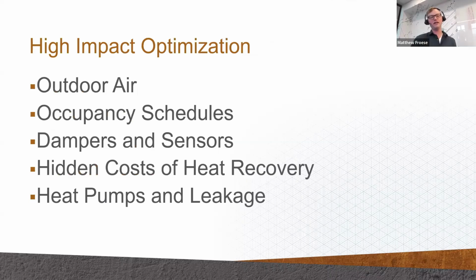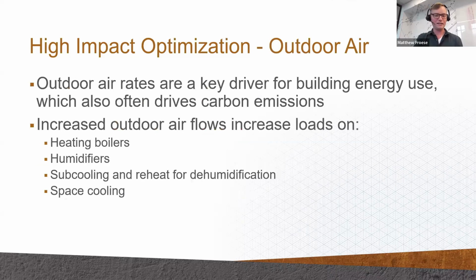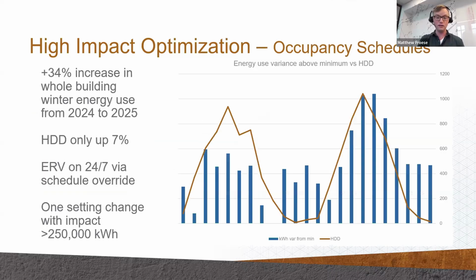So some areas of high impact optimization here. We're going to talk a little bit about outdoor air and ventilation management, a little bit about occupancy schedules, really basic fundamentals, some stuff about dampers and sensors, a little bit about heat recovery, and then heat pumps and refrigerant leakage. I'm going to move fast. So outdoor air is a big deal. We need enough ventilation to keep people healthy and safe, but it drives loads in a really big way, especially in our climate where we get really hot and really cold.